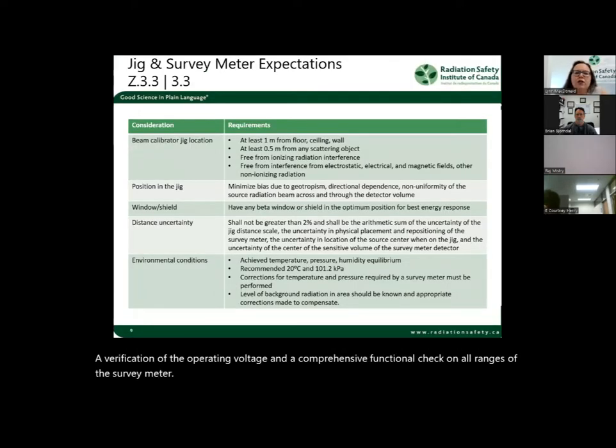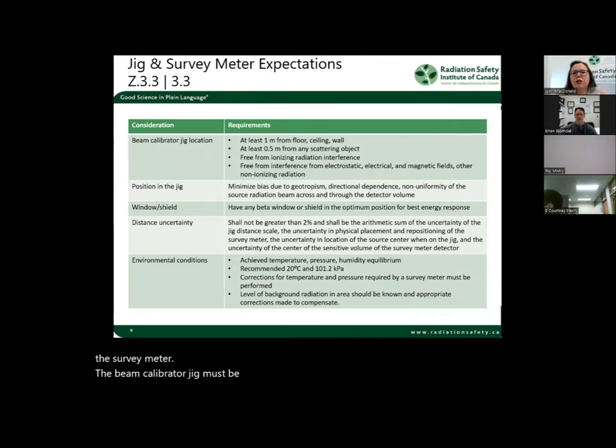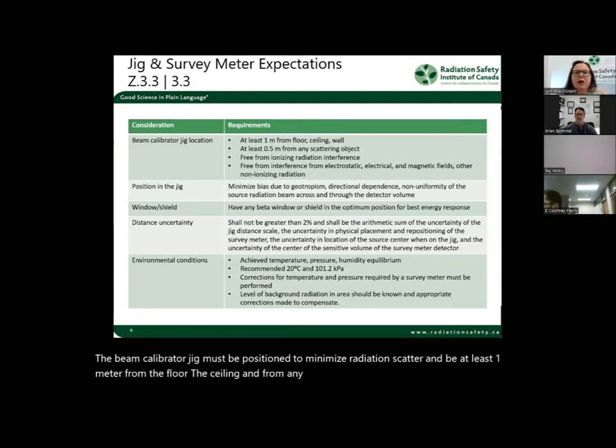The beam calibrator jig must be positioned to minimize radiation scatter and be at least 1 meter from the floor, the ceiling, and from any wall. The distance between any scattering object and the source must be at least 0.5 meter. The beam calibrator jig must be located in the following manner: in an area free of interference from sources of ionizing radiation other than the calibration source, in an area where electrostatic, electrical, and magnetic fields and other non-ionizing radiation will not affect instrument response.